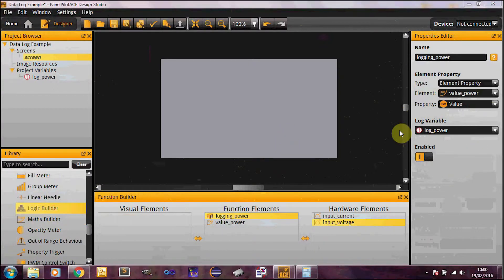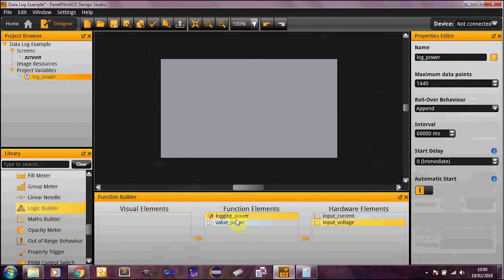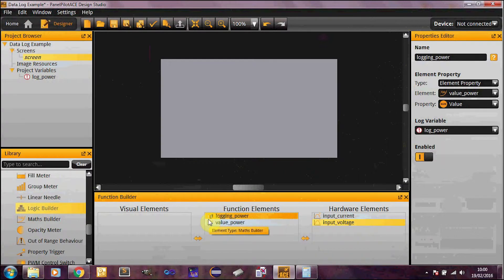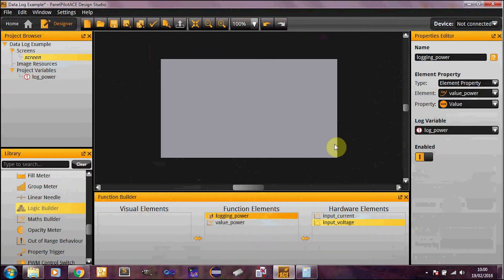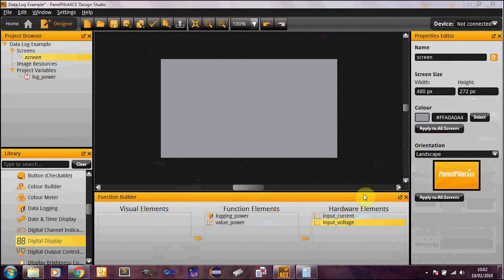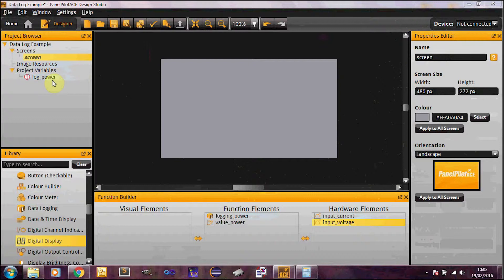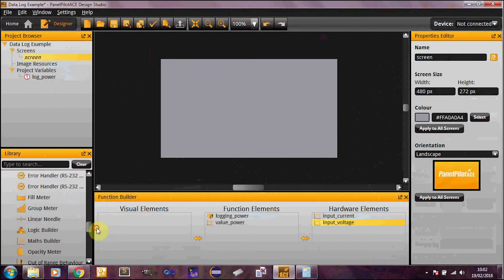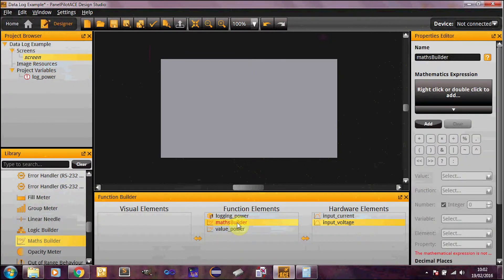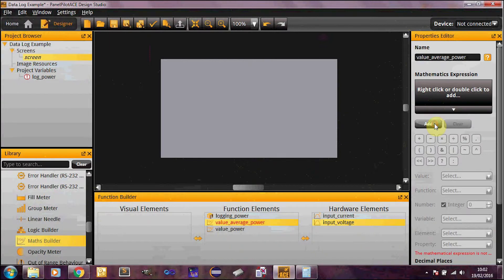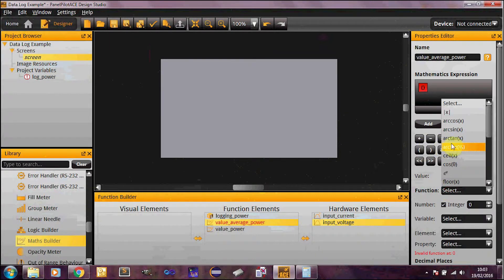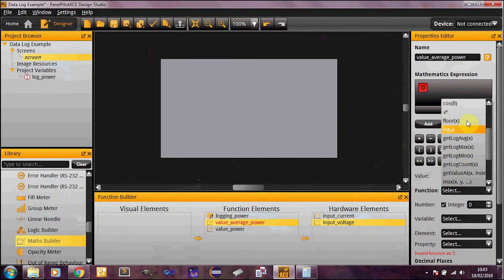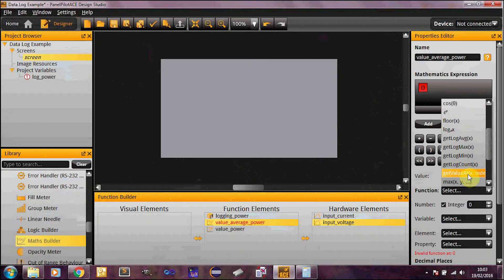So there you go. There are your two main elements. Now you've got your log variable, which is now linked to your logging element here on this page. And as I said before, if you have multiple pages and you want the logging to be occurring on any of those pages, just make sure this element is copied and pasted to all of the other pages. So now that we've gone through the logging element and the logging variable here, the next thing I want to show you is how to get variables results from that data. So for example, the maximum value in a log, the average value in a log. So what we've done is we've actually added several functions to the maths builder. So what I'll do here, I'm just going to display the average power. And in order to get that, if you click on the functions here, you see these new get log average, get log max, min, count, value at functions.